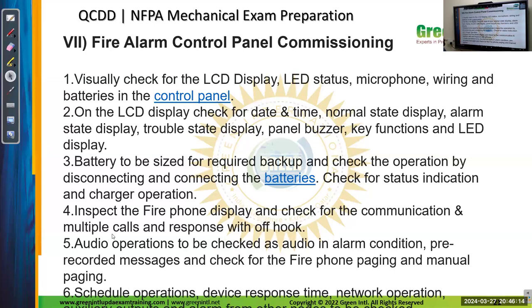Fire alarm control panel commissioning. Visually check the LCD display and LED status, microphones, wiring, and batteries in the control panel. So it's like a checklist. You have to check the trouble state display, whether the panel buzzer function is working or not, whether the batteries are working or not, and inspect the fire phone display and check the communication, multiple calls and response with off hook.